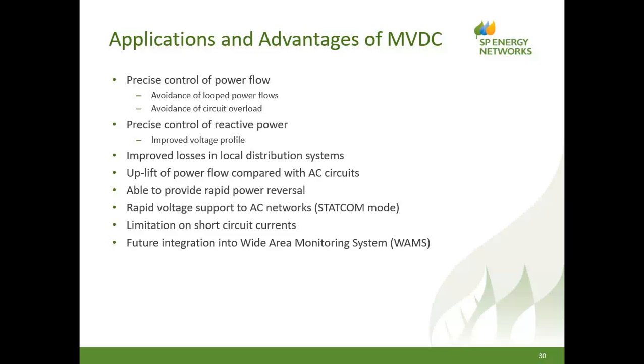We can precisely control the reactive power, both absorption and generation. And this will allow Scottish Power to improve the voltage profile at both ends of the link. If we can improve the voltage profile, we can improve the losses in the local distribution system. I've mentioned we have an uplift of power compared with AC systems.